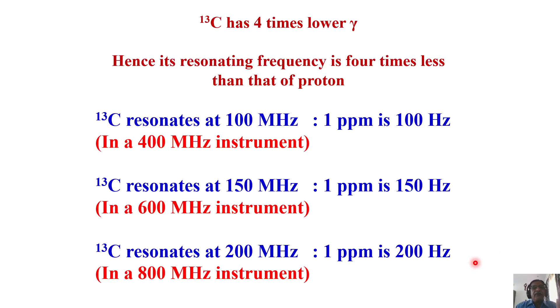Remember, it is not 400, it is 100 hertz, because the resonating frequency of carbon is 100, whereas that of proton is 400. So proton 1 ppm is 400, whereas carbon 1 ppm is 100 hertz. Similarly, at 600 megahertz, carbon comes at 150, so 1 ppm is 150 hertz. Same way, carbon resonates at 200 megahertz on the 800 megahertz spectrometer, where 1 ppm in proton is 800, whereas in carbon-13 on the same spectrometer, 1 ppm is 200 hertz. You understood the point.